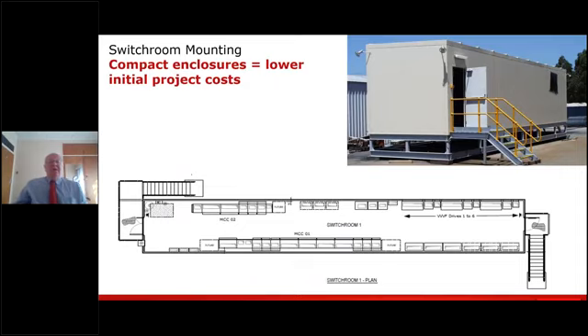Now, if we take a look at what we call the footprint, the size of the drive: electrical equipment on mines is usually installed in areas known as switch rooms or control rooms. Some call them substations, others call them e-houses. These switch rooms are quite often constructed from normal 20-foot or 40-foot shipping containers. These are often used when mines are in hard to reach remote areas, because it's easy to load them onto the back of a truck, load them onto a ship if necessary, sail them up the coast, offload them, put them on the back of a truck, and then take them to site.